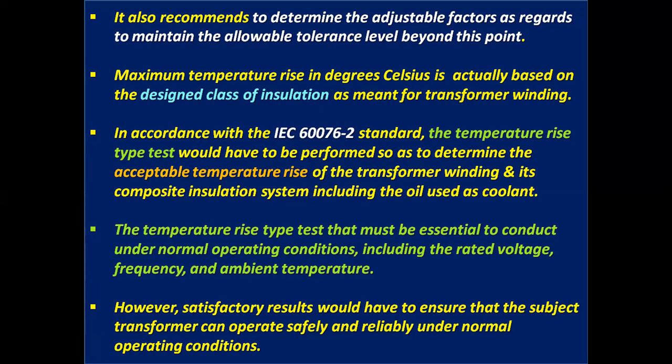standard, the temperature rise type test would have to be performed so as to determine the acceptable temperature rise of the transformer winding and its composite insulation system, including the oil used as coolant.